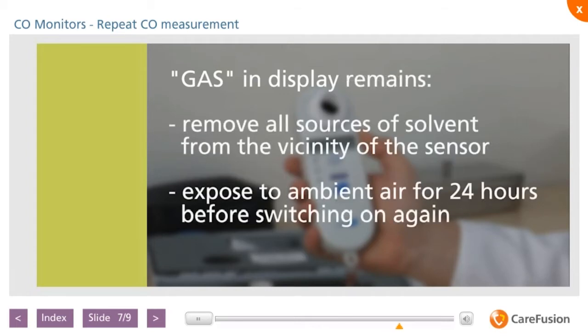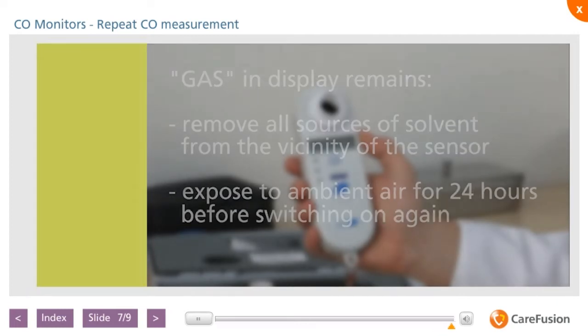If the same message appears again, then this indicates possible contamination of the sensor with a solvent. In this case, remove all sources of solvent from the vicinity of the sensor and expose to ambient air for 24 hours before switching on again.